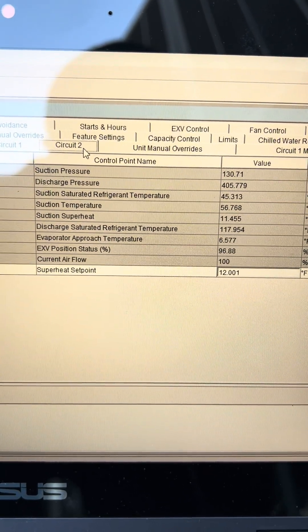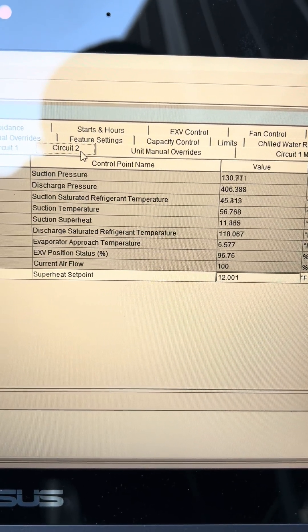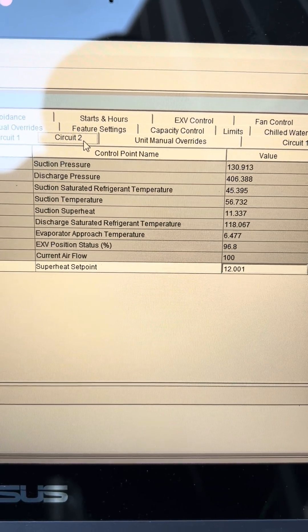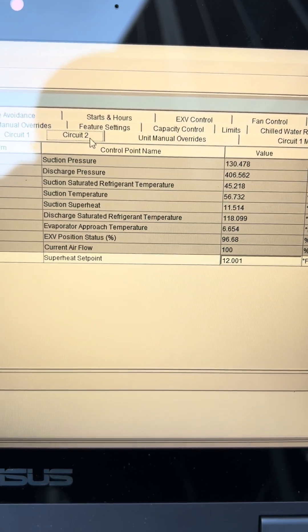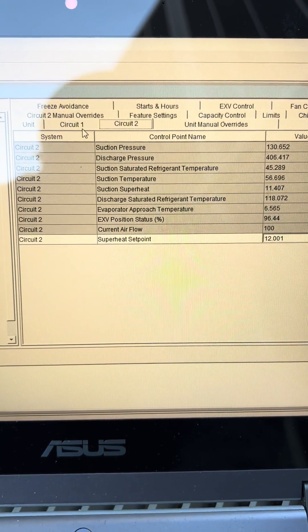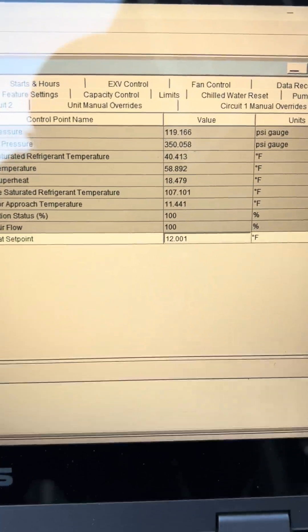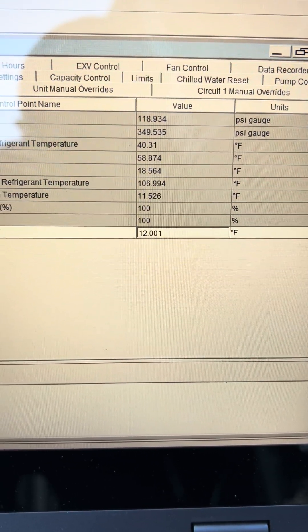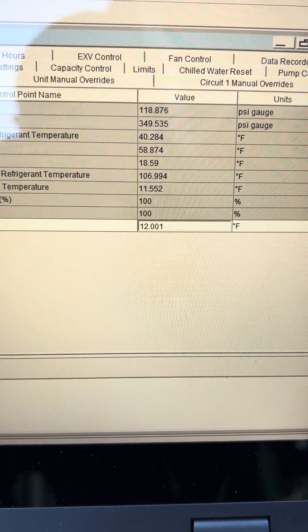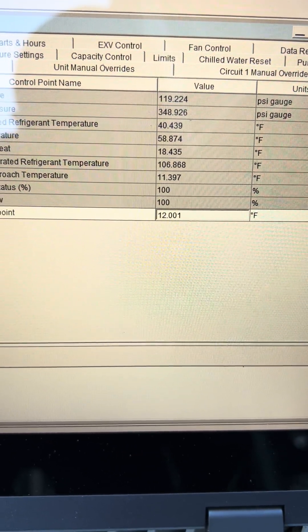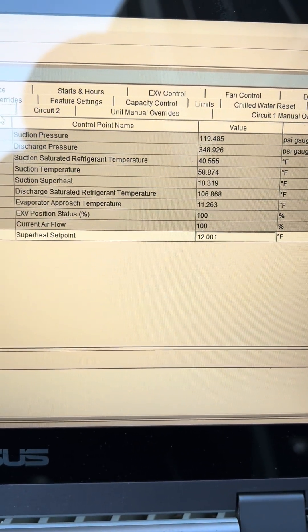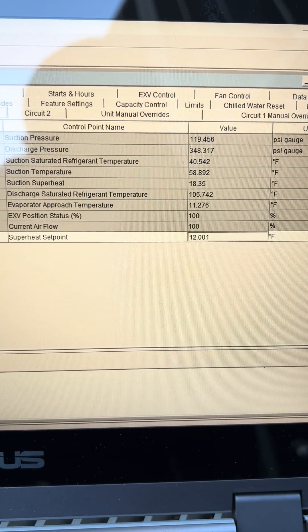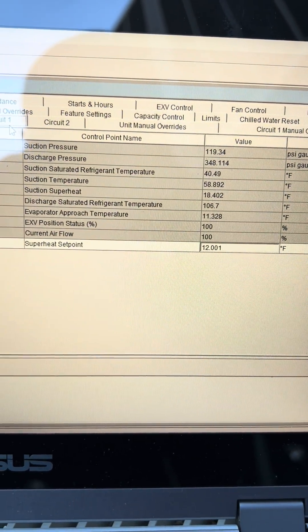Circuit number one, so we have 119, 350. Superheat is at 18, my valve is at 100 percent EXV. Yeah comment if you think that we got a refrigerant problem right. I'm going to close this off.